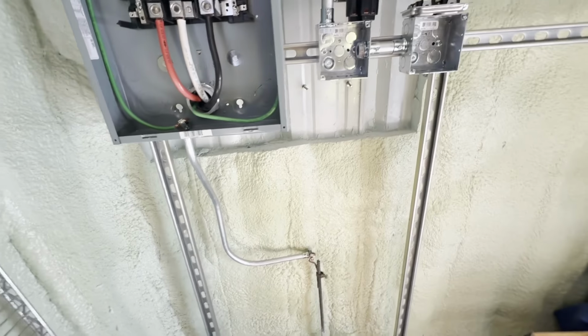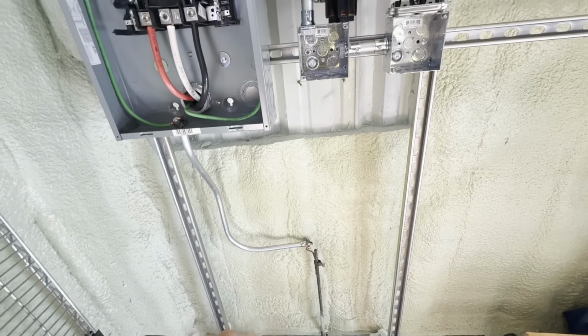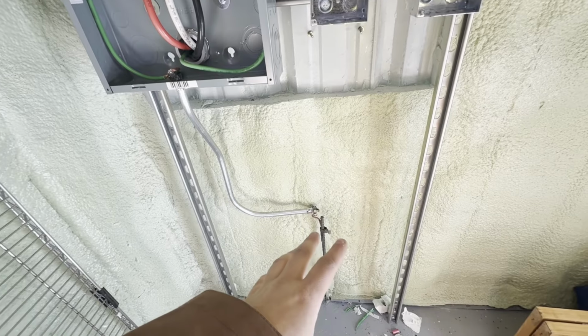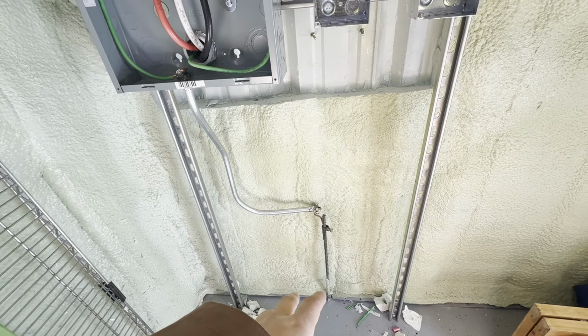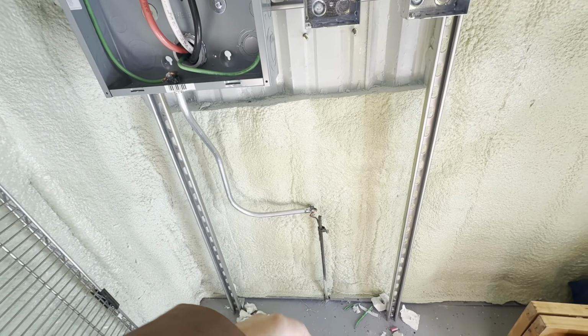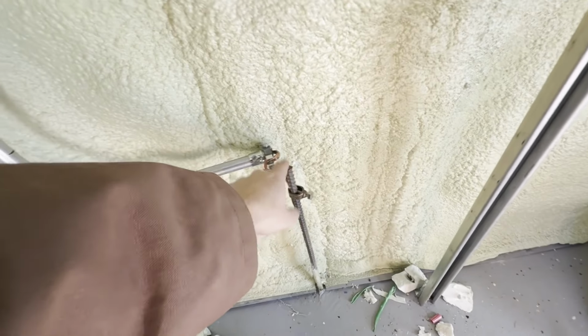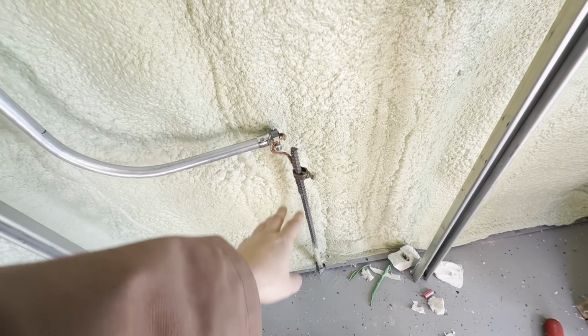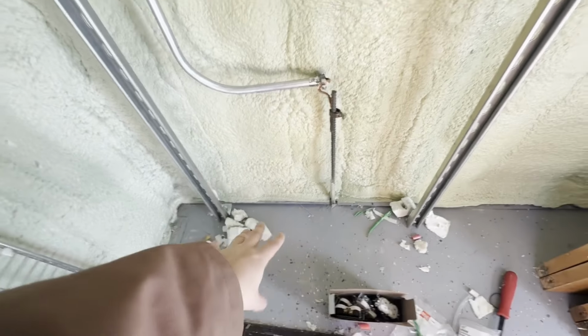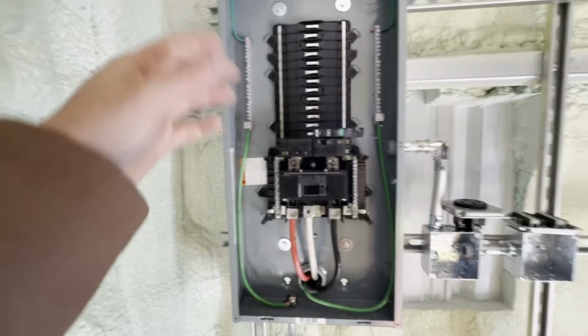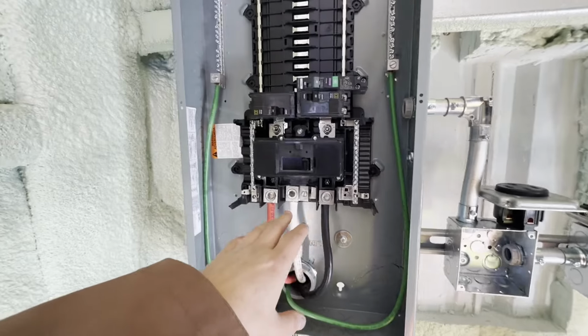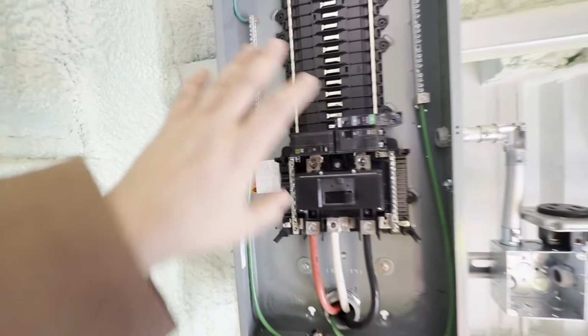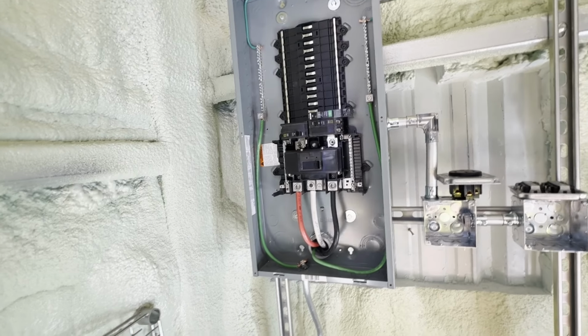So for grounding out here, the shop is a metal building, and I've got a Ufer ground—this is rebar that's tied into all the rest of the rebar in the slab, and that's going to be my ground point. Just like in the house, the neutral and ground are not bonded here, because they get bonded out at the meter pedestal, and that's the only place they get bonded in this configuration.